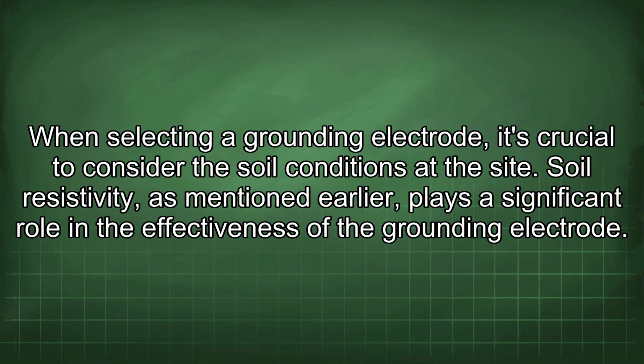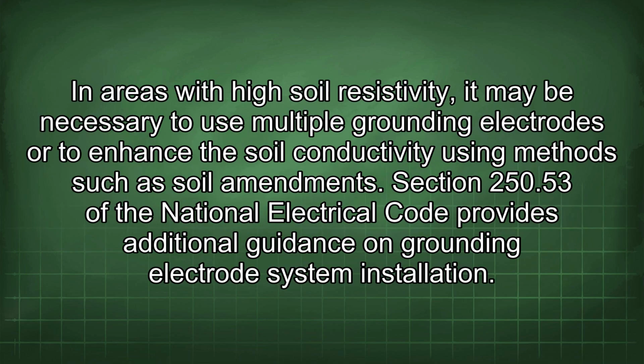When selecting a grounding electrode, it's crucial to consider the soil conditions at the site. Soil resistivity, as mentioned earlier, plays a significant role in the effectiveness of the grounding electrode. In areas with high soil resistivity, it may be necessary to use multiple grounding electrodes or to enhance the soil conductivity using methods such as soil amendments.